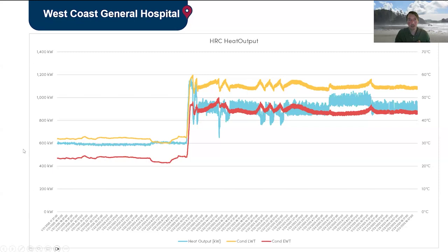So this wasn't really something well understood, I think, by many of us, in that we had different modes available within the programming of these heat recovery chillers. As soon as we had switched into that low temperature mode, you can see the difference in heat output. The output is on the left side of the axis, and on the right side, you can see the various different temperatures for the entering and leaving of the condenser. But just to stick with the heat output, we're going from 600 kilowatts up to about 900 kilowatts just by switching into that lower temperature state of operation.